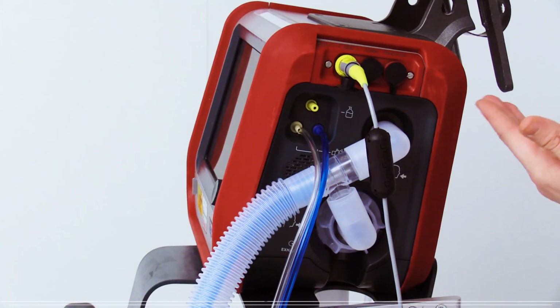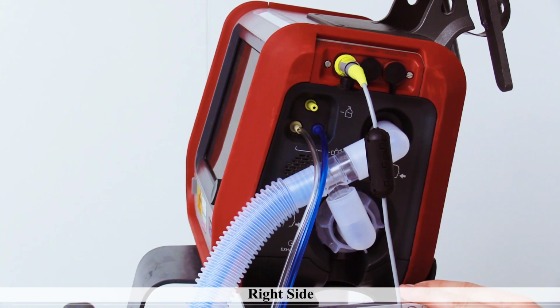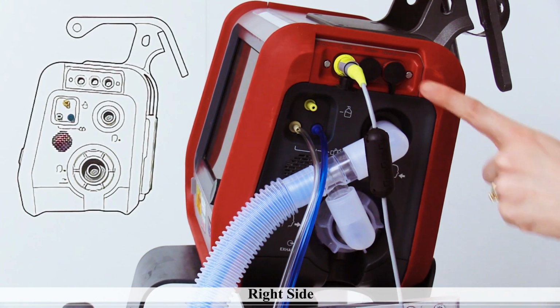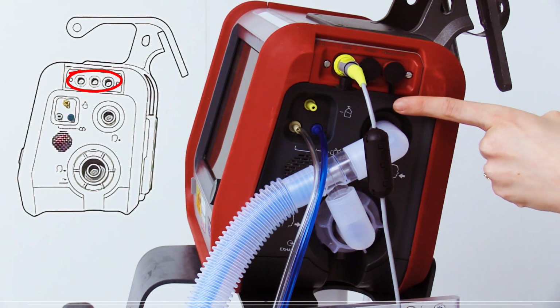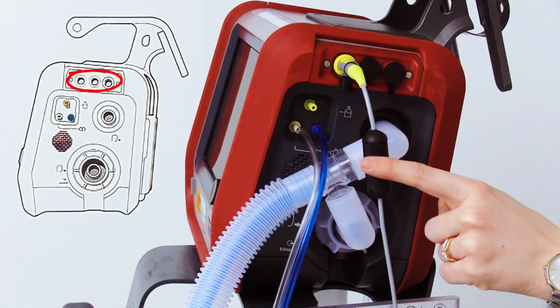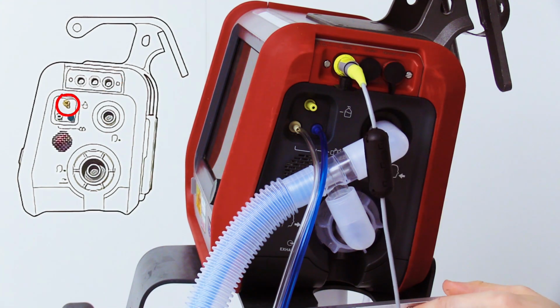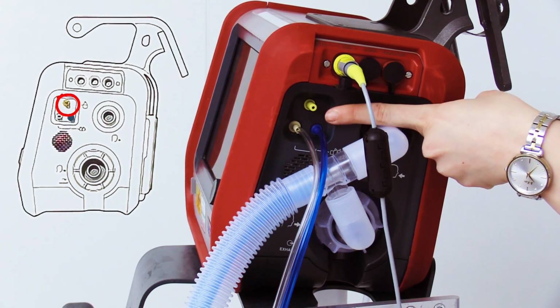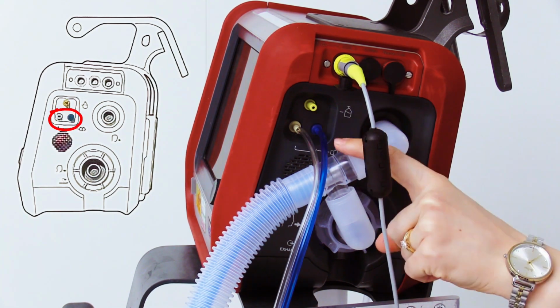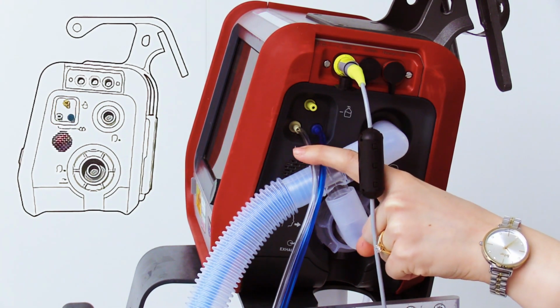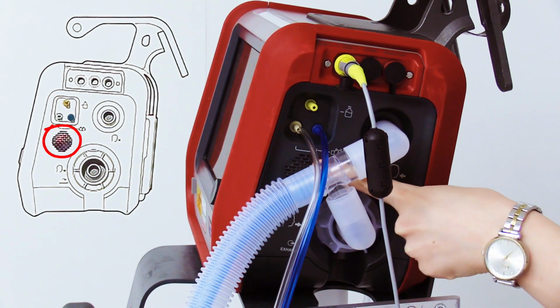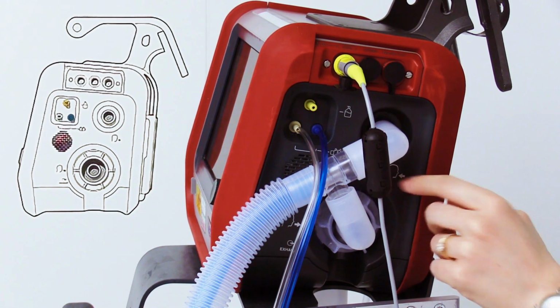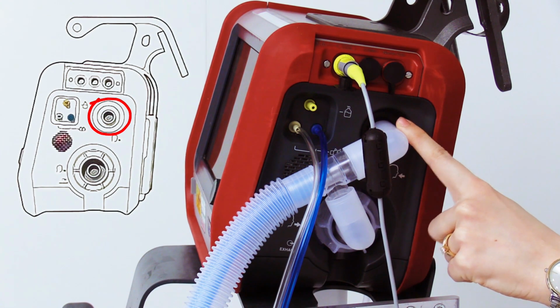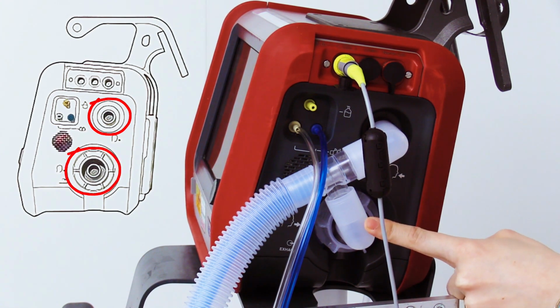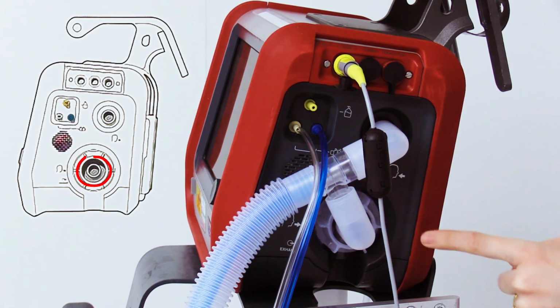On the right side of the ventilator, we find the key ports for connecting the breathing circuit set. These are communication ports with options for end-tidal carbon dioxide. Then we have the pneumatic nebulizer port. These are the flow sensor connection ports, which are blue and white in color. And below that is the alarm speaker. Here are the patient inspiratory and expiratory ports for circuit connections. And this is where to connect the expiratory valve.